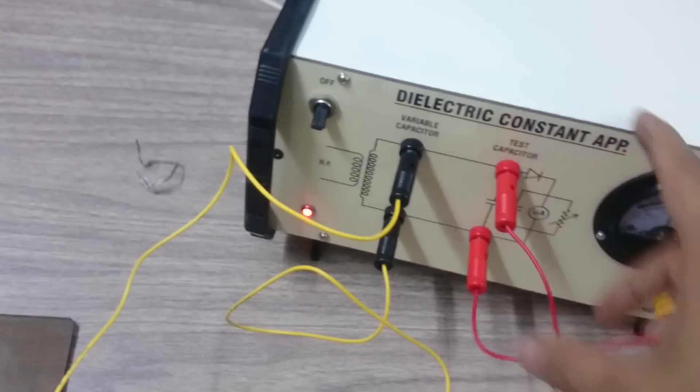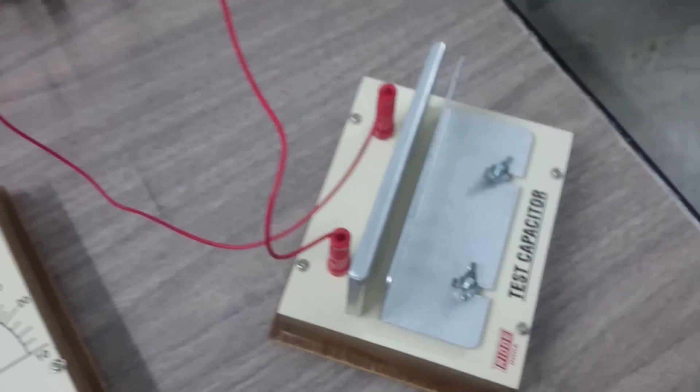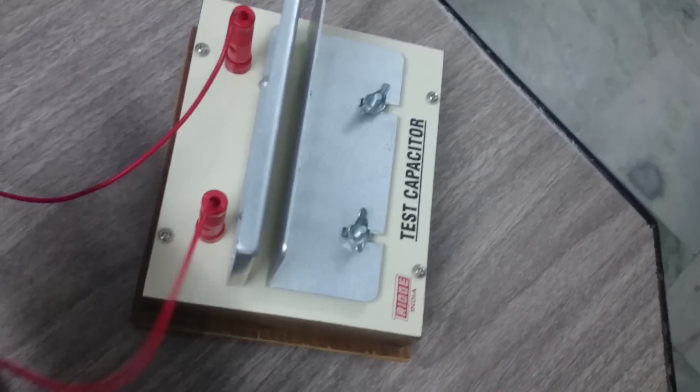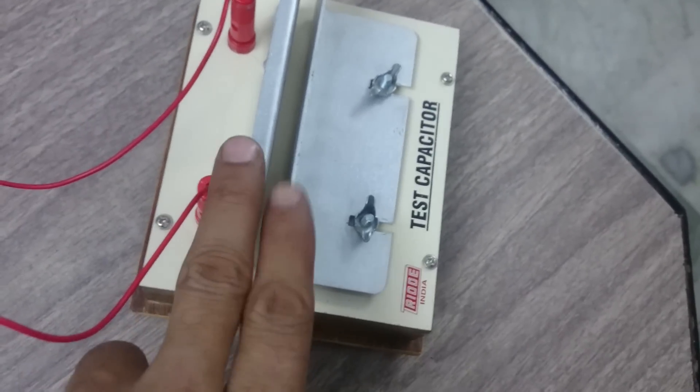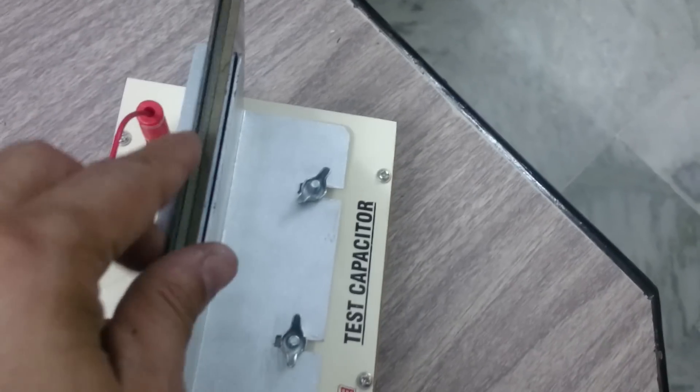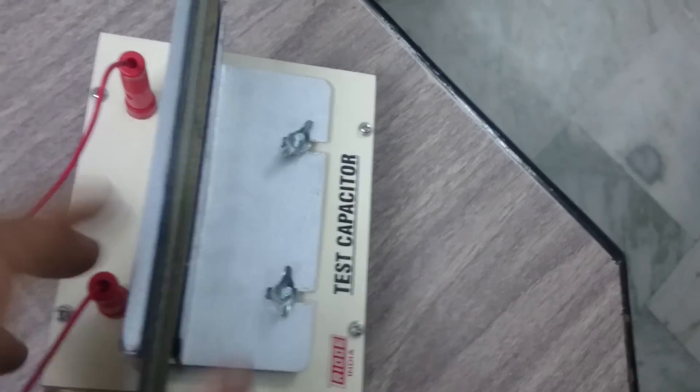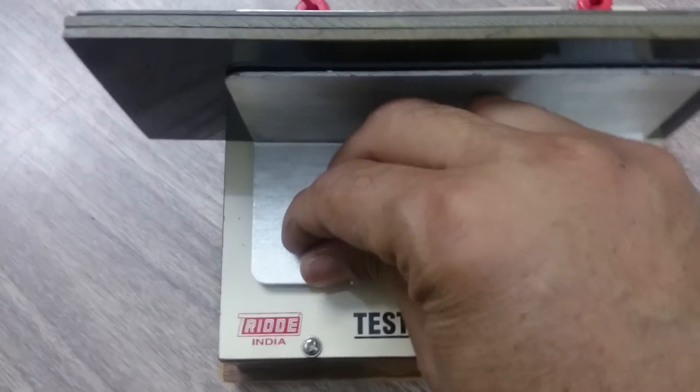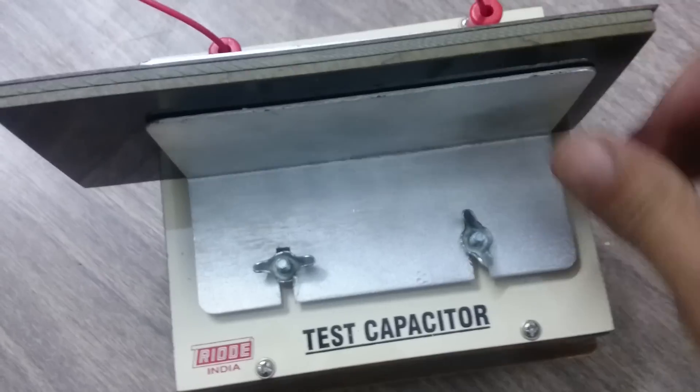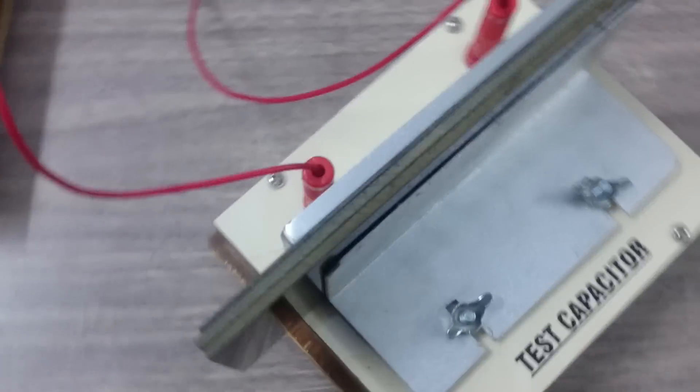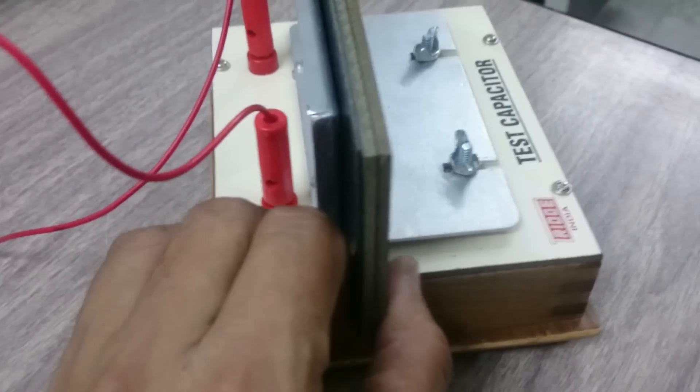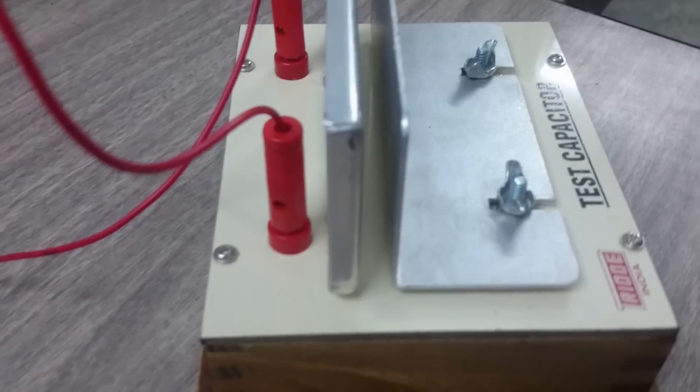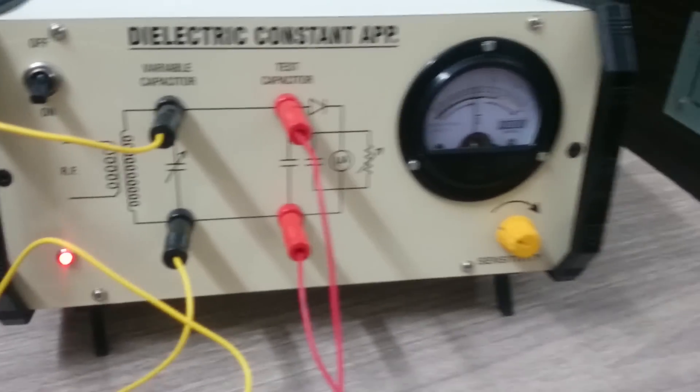These are inserted. Now without dielectric, you should know the distance between these two plates. By inserting these plates you can check the distance. These are easily insertable. You can tighten it. This gap is 7.5mm. First, check the sensitivity.